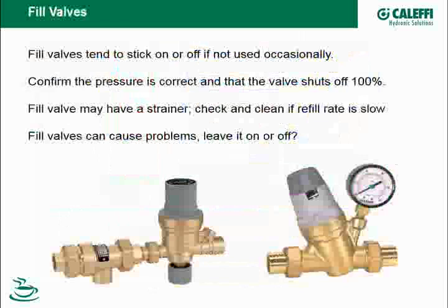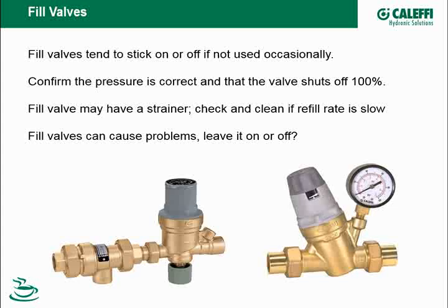Fill valves, this is one that you're going to come across probably most often on the troubleshooting call. And one of the things that can happen with a fill valve, if they don't get used for a period of time, and then you go there and you take some fluid out of the boiler to check the fluid quality, or you change a pump, or you do some work on it, you've got to refill the system. One or two things can happen with these valves. Either they'll stick shut where they won't refill. When you go to use them again, you drain some water out and you turn that valve on, you tap on it trying to get it to fill. And the opposite thing can happen. They'll fill up and they'll keep overfilling because that little seat in there, if it hasn't been used for a while, with a little rubber washer, little diaphragm that comes down on the seat, sometimes it'll get stuck, and then when it opens, it'll rip it or put a little tear in the washer, just like when a faucet washer goes bad.